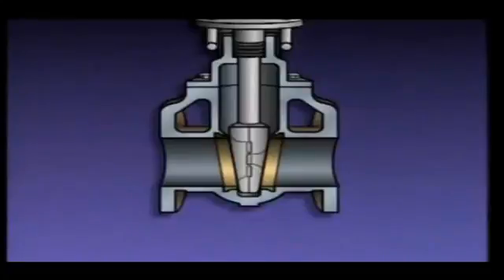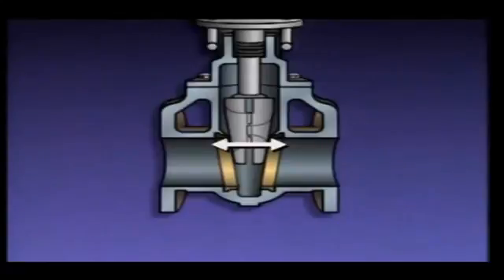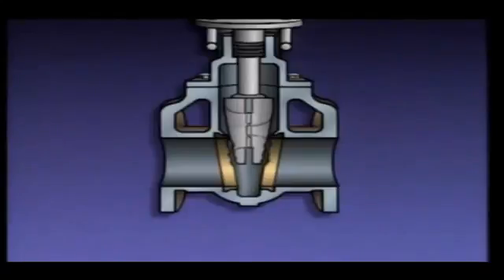Gate valves are normally used in on-off applications, but in an emergency they can be used to throttle flow. However, long-term use as a throttling valve can damage a gate valve. When the disc is raised slightly, fluid flow creates turbulence, which causes the disc to swing from side to side, chattering against the seat. This chattering causes wear on the seat and disc, and eventually the valve will not shut off flow when completely closed.